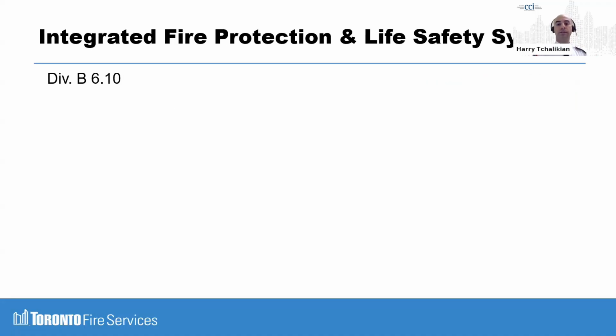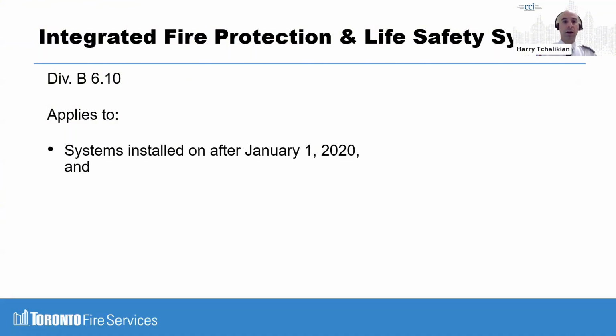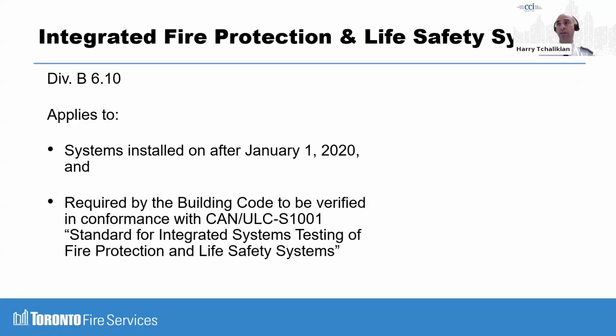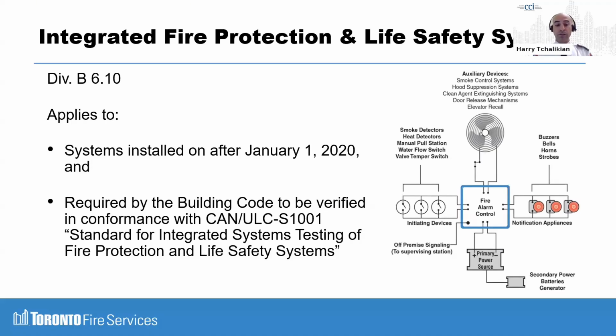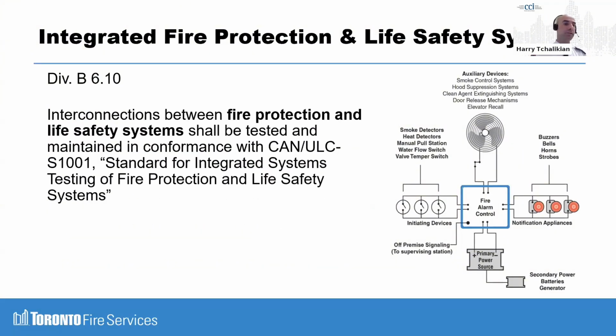Next, we get into integrated fire protection and life safety systems. This is brand new, quite significant. Applies to systems installed on or after January 1st, 2020, required by the building code to be verified in conformance with CAN ULC S1001, standard for integrated systems testing of fire protection and life safety systems. So it applies to multiple systems that are connected to each other to make sure nothing falls between the cracks in terms of these systems communicating with each other. So the fire alarm system is the heart of this requirement. We'll go over that.